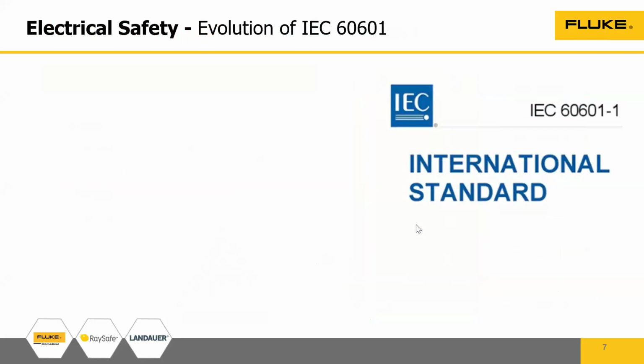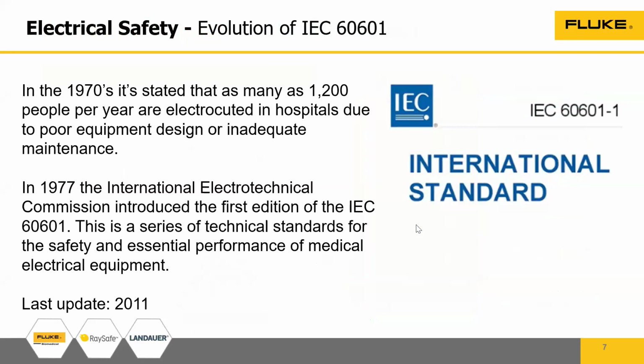Based on this small background, I'll bring you to the electrical IEC standards and how the IEC evolved for medical devices. The International Electrotechnical Commission had some data from the 1970s. These data are not from India; in India, it would most likely be much more. Around 1200 people per year were electrocuted in hospitals due to poor design of medical equipment.